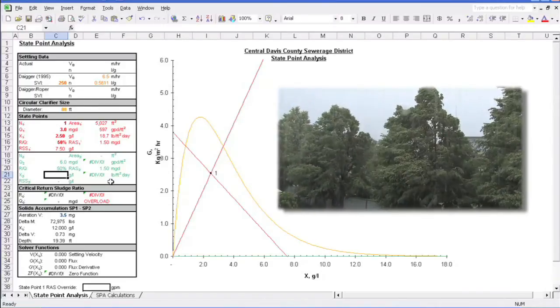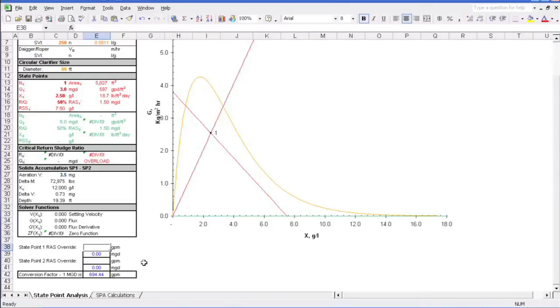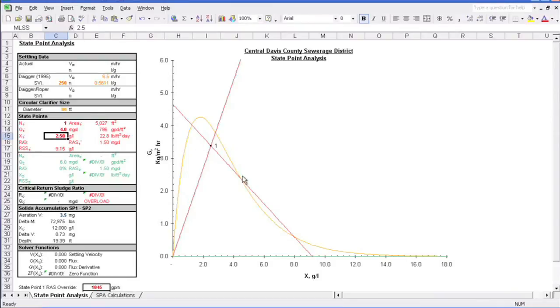So it's a rainstorm. Hits your system and the flows begin to rise. Before you know it, your influent flow has risen to 4 MGD and your RAS pumps don't automatically adjust with the flow. For this, we need to override the RAS rate. We see that 50% of 3 MGD is 1.5 MGD of RAS. Now we need to enter in the value in gallons per minute in the override box down here, which conveniently gives us the conversions to MGD. And because we're really smart, we know that 1.5 MGD is 1045 gallons per minute. So we can enter that in here, and it overrides up here above. And now we can change our flow to 4 MGD. And as you can see, our state point stays under the curve, but our underflow line doesn't. We know we are going to fail in thickening. So what can we do?